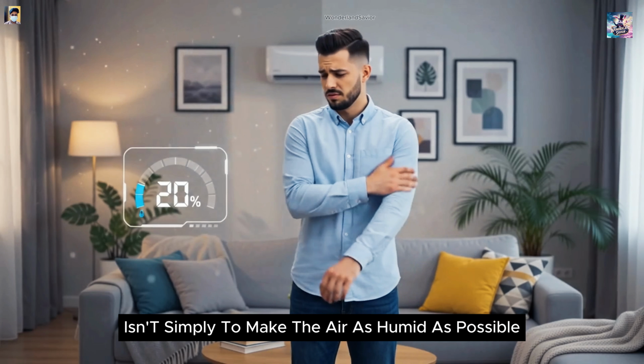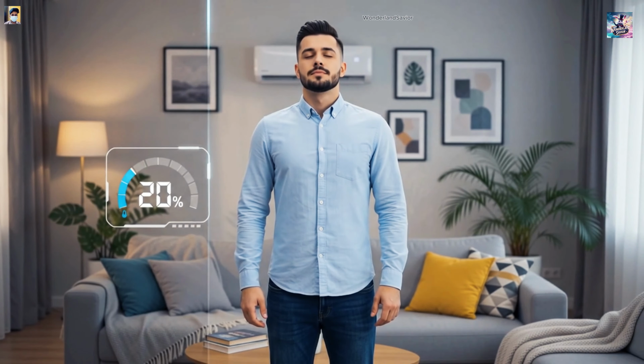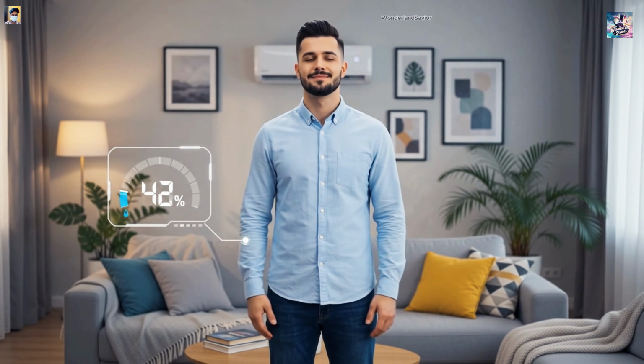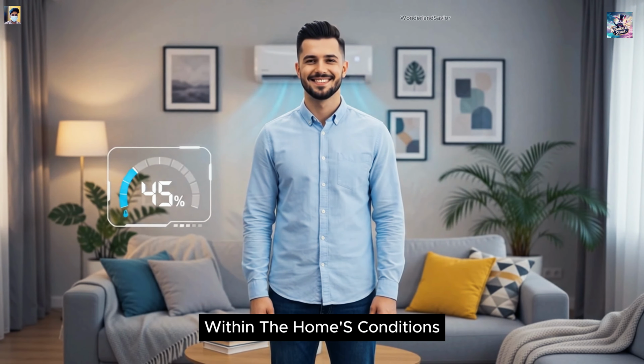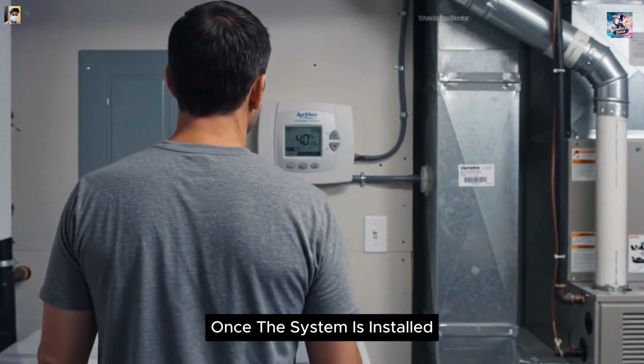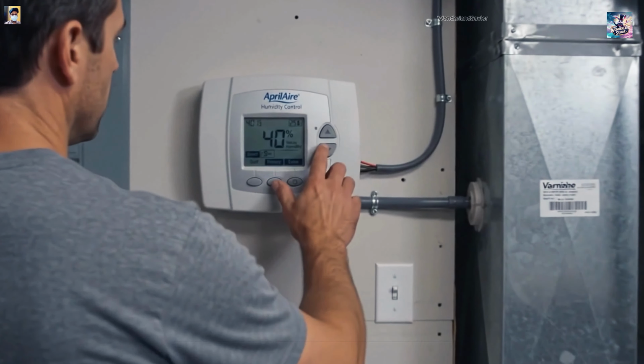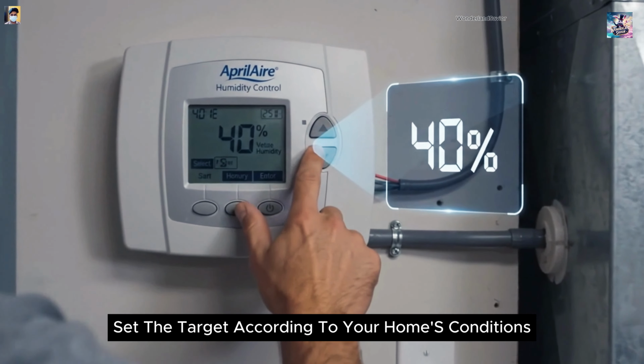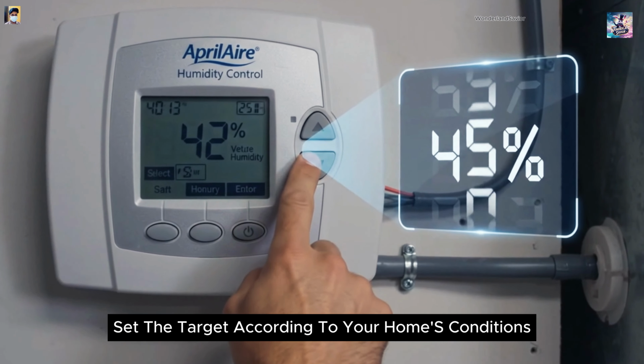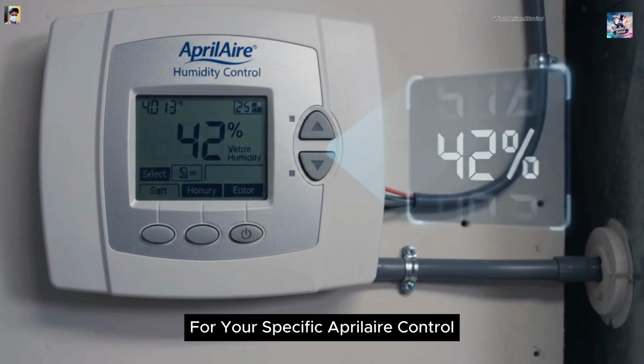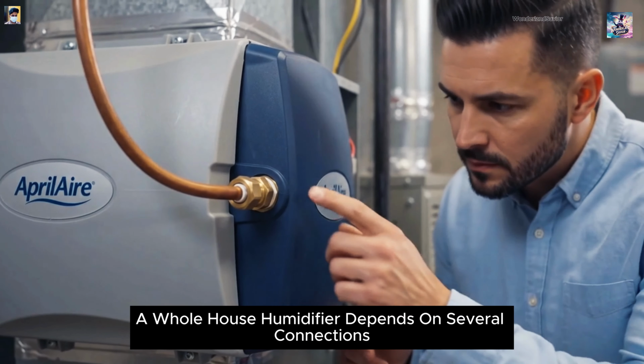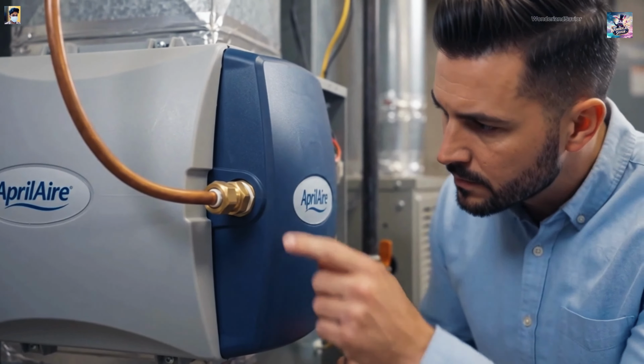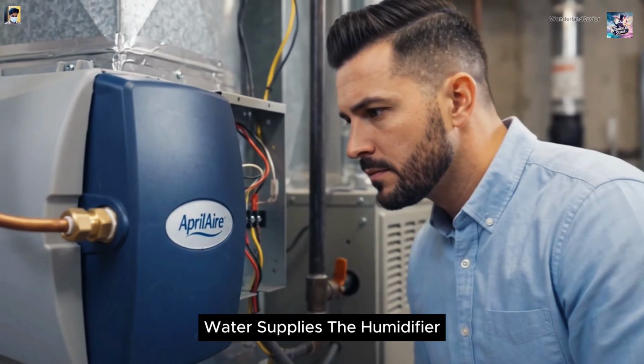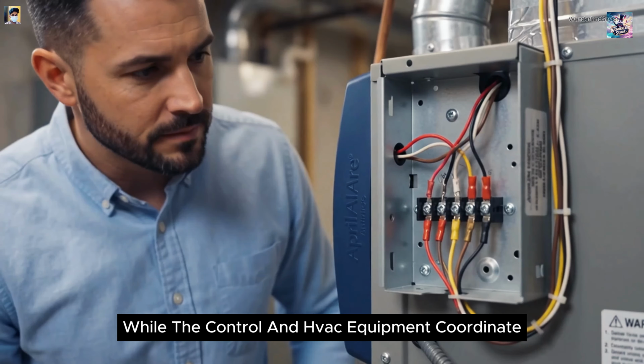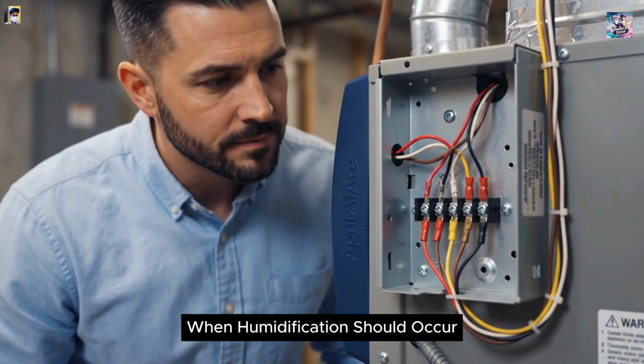The goal isn't simply to make the air as humid as possible. Instead, the humidifier works with its control system to maintain the selected humidity level within the home's conditions. Once the system is installed, the humidity control determines when additional moisture is needed. Set the target according to your home's conditions and the instructions for your specific Aprilaire control. A whole house humidifier depends on several connections working together. Water supplies the humidifier, while the control and HVAC equipment coordinate when humidification should occur.